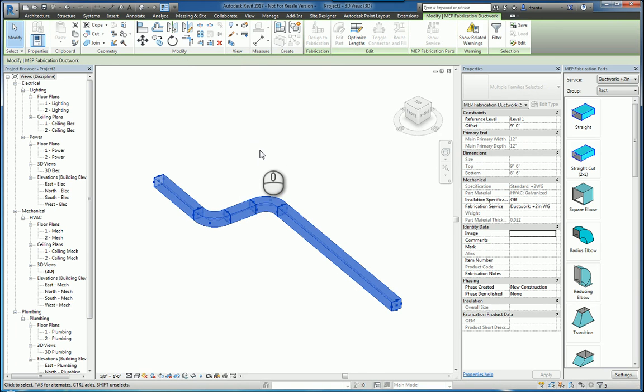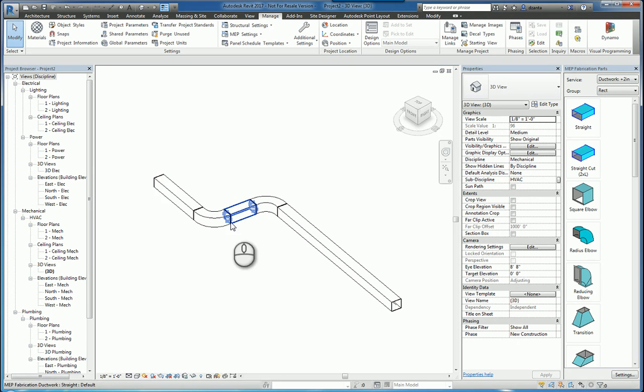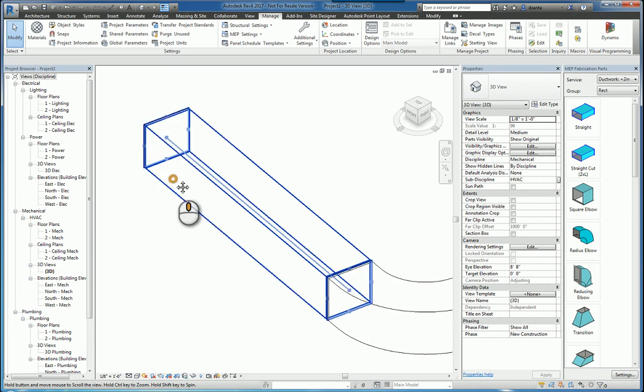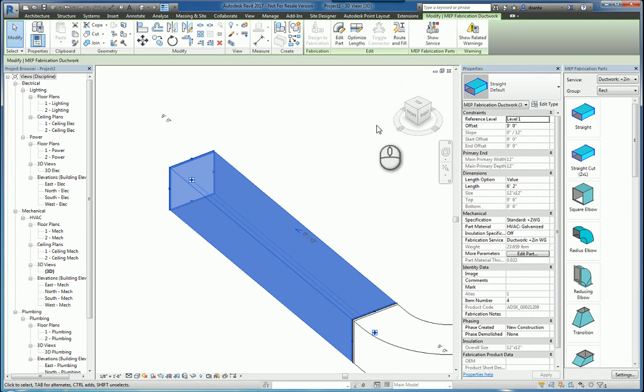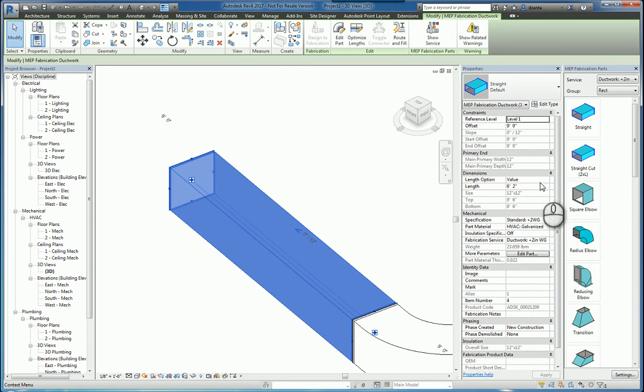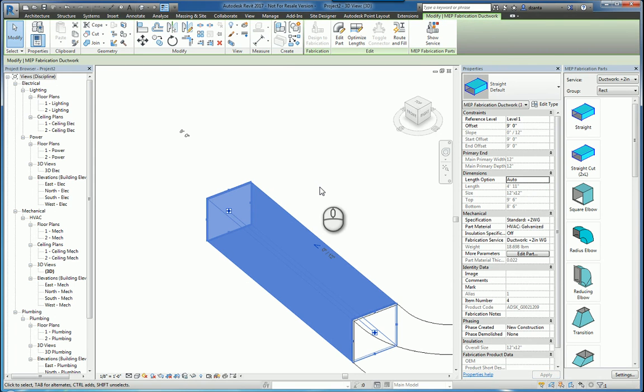What Revit will do is transfer and change those ducts to fabrication-level parts. You can see they're slightly different — if you zoom in, you can see that they actually have the fittings on both ends. If you select one of them, you can see that there is a Length option, and the length is whatever that initial design was, which is set to Value. If you switch it to Auto, it's going to default to 4'11" and adjust accordingly.